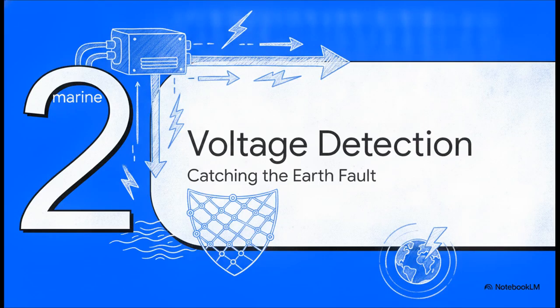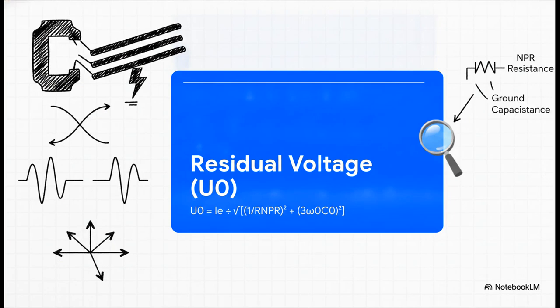Moving right along to method 2, catching the earth fault via voltage detection. Because honestly, we don't just rely on watching current. We build a safety net by watching voltage too. So method 2 measures residual voltage, often called U0, taken directly from an open delta voltage transformer right on the bus bar. Normally, just like current, phase voltages naturally sum to 0, but during a fault, they distort. U0 rises according to a very specific mathematical relationship. It's the earth fault current divided by the combined admittance of the NPR resistance and the network's natural ground capacitance. Basically, this gives the system a mathematically verifiable, foolproof way to confirm an active fault.